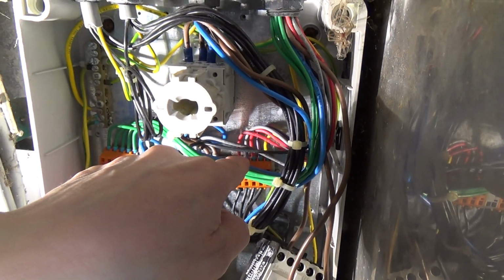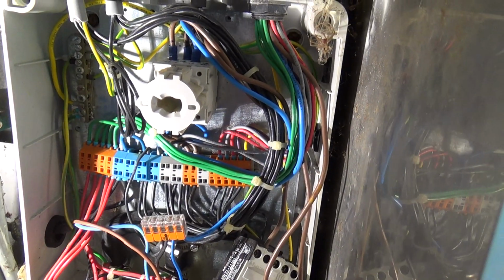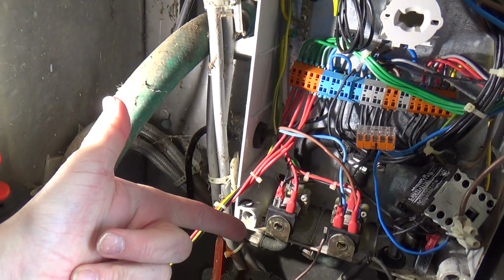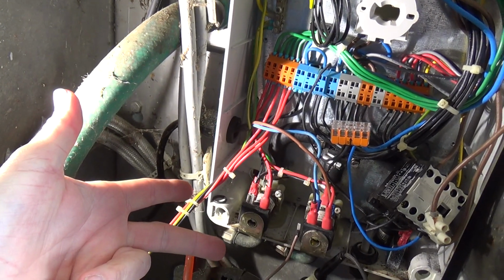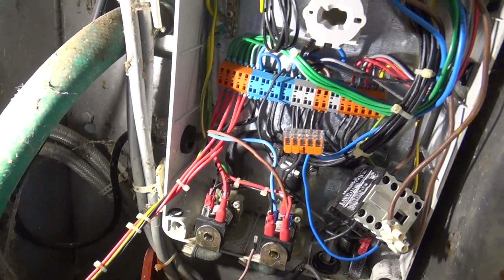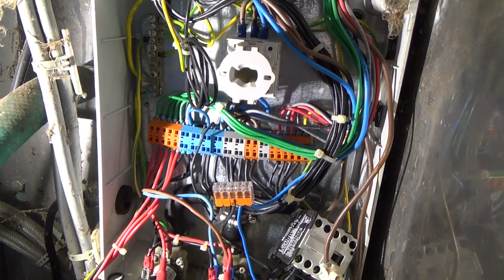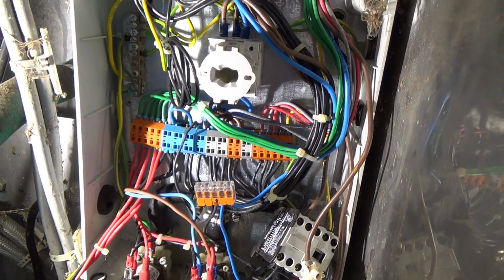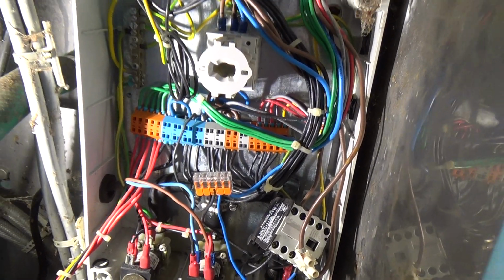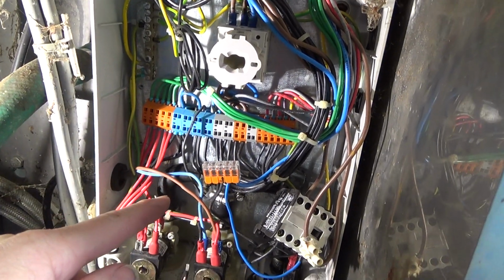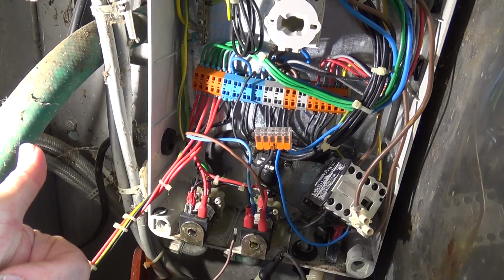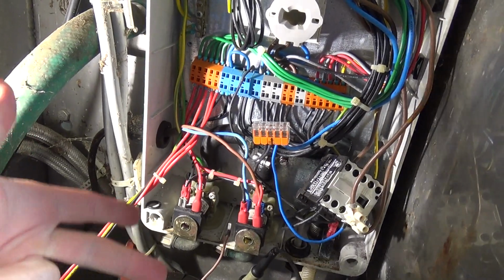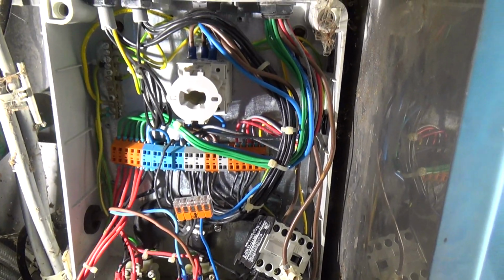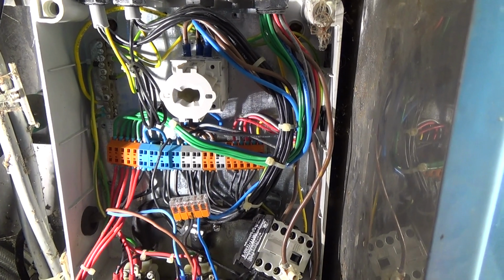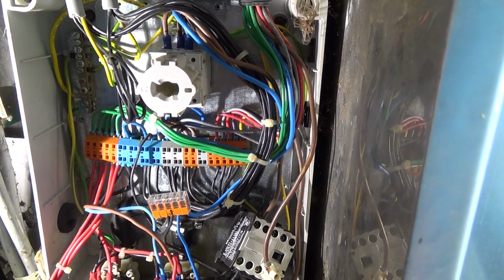Okay, so we've got a short showing on the grey, the red and the purple, which, now I think about it, is probably the booster pump, the cooling solenoid for one compressor and the cooling solenoid for the second compressor. So that they will also show, and there's a priority relay on this as well, so if it's running, the compressors are running an ice builder at the moment. If the tank calls for cooling, when the cooling signal goes out from here, it energises a relay to disconnect the cooling feed to the ice builder and switch over to the tank, so the compressors are not trying to run two things at once and doing neither of them well. So that relay would also have a connection to earth via the neutral connection.